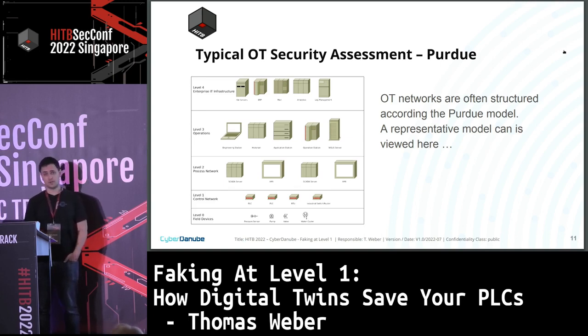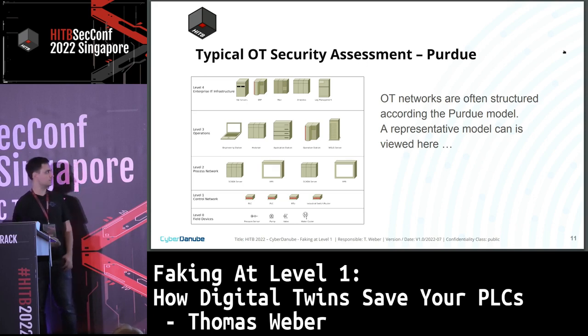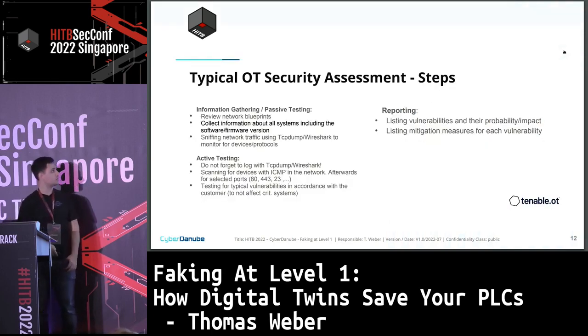One of our customers had just one problem with one of his switches, which was broadcasting all information, all packets through the whole switch, because we don't know, maybe the switch table was flooded or not. We don't know. And then the whole OT network was stuck. It was just denial of service of the whole network. So it's not even a malicious attack. It was just failure. That's it. And for those cases, it's really wise to do this kind of separation between those levels.